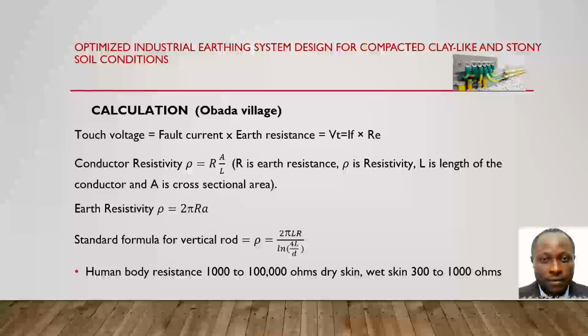But for earth resistivity it is different. The resistivity is 2 pi R A. 2 pi R A, because you need the circumference of a circle to get that done. So here you see 2 pi multiplied by the resistance you read from the meter, and A is the distance between your rods that you bury. Everything must be in meters for uniform units.